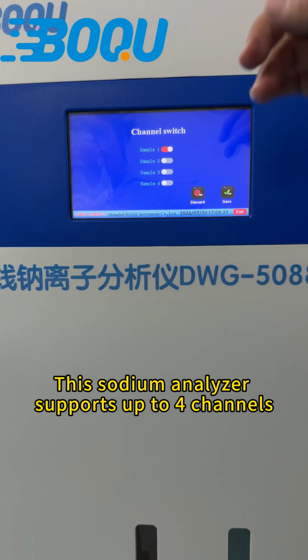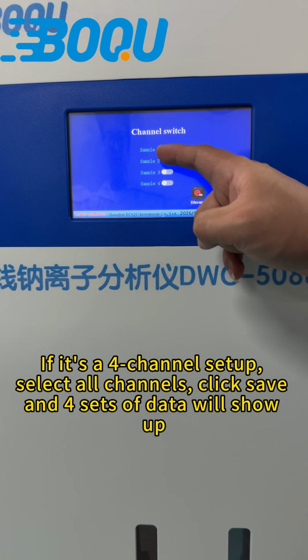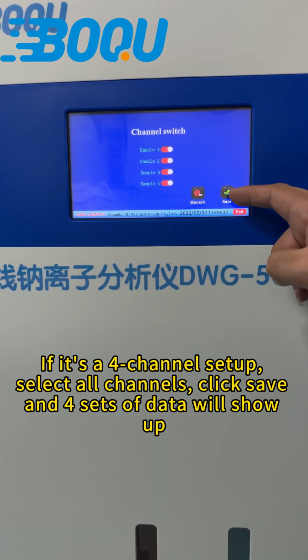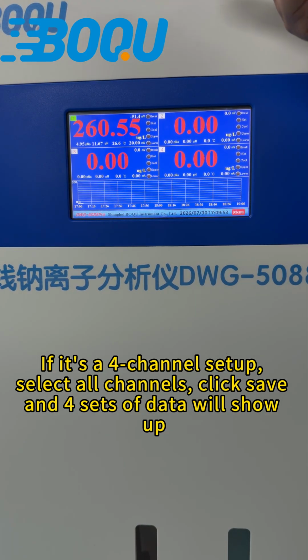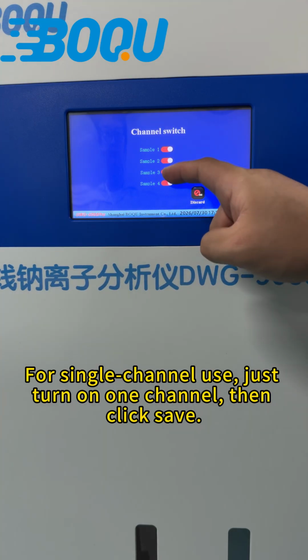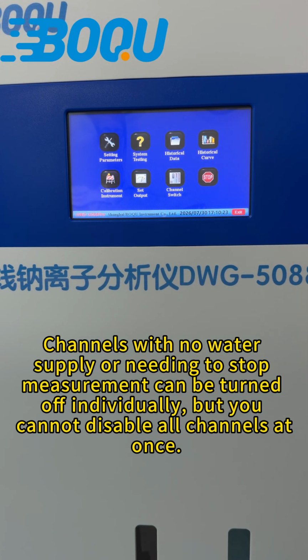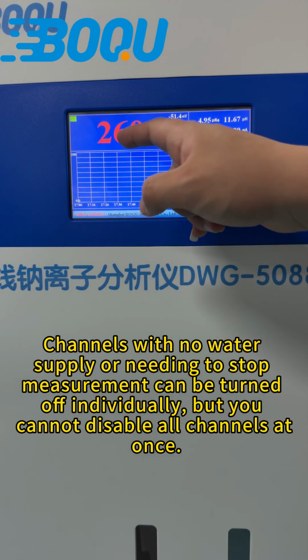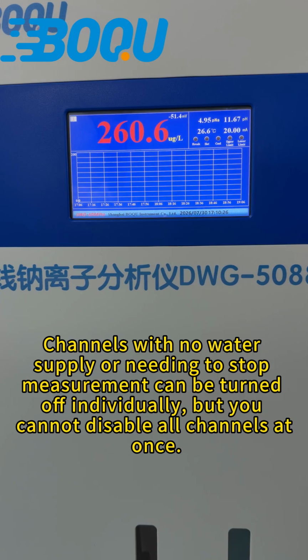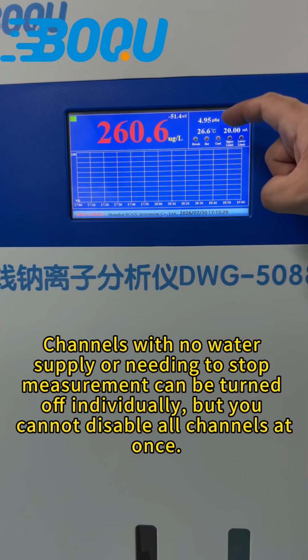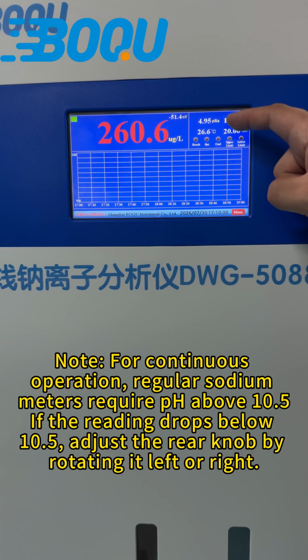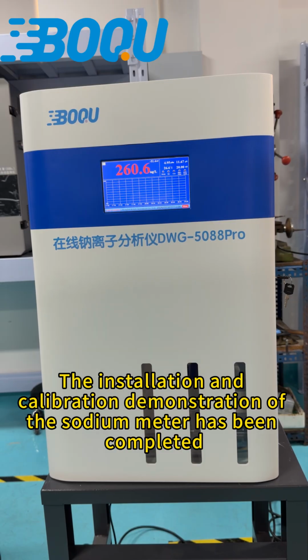This sodium analyzer supports up to 4 channels. If it's a 4-channel setup, select all channels, click Save, and 4 sets of data will show up. For single-channel use, just turn on one channel, then click Save. Channels with no water supply or needing to stop measurement can be turned off individually, but you cannot disable all channels at once. Note: for continuous operation, regular sodium meters require pH above 10.5. If the reading drops below 10.5, adjust the rear knob by rotating it left or right. The installation and the calibration demonstration of the sodium meter has been completed.